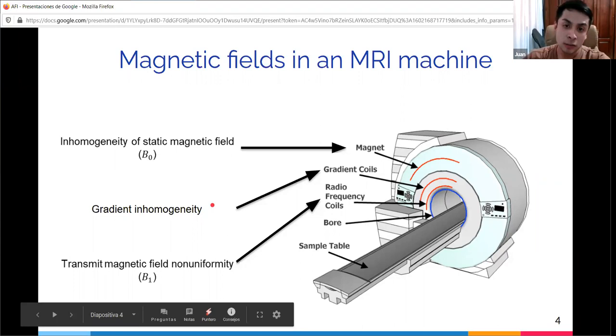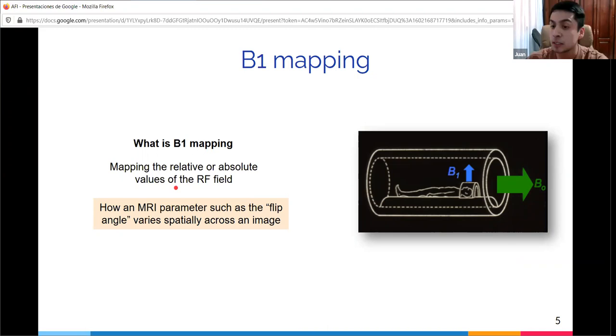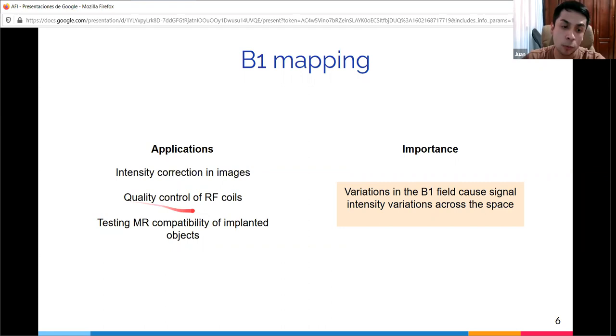This establishes what B1 mapping is. B1 mapping measures the relative or absolute values of the radiofrequency field to know the spatial distribution of the transmitted RF field. It aims to find an MRI parameter which varies spatially across an image. The flip angle is frequently taken as a direct measure of the B1 field because the flip angle is a function of the strength of the B1 field. B1 mapping fulfills a wide range of applications, such as quality control of RF coils or testing MR compatibility of implanted objects.